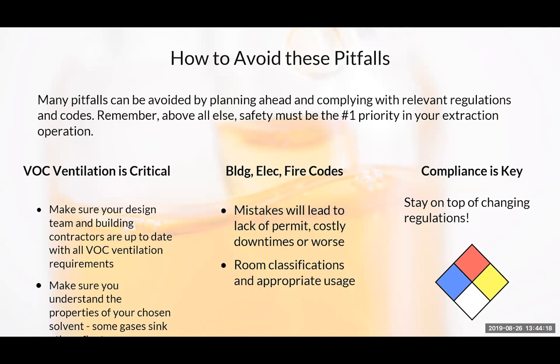It's pretty straightforward. The pitfalls we've already covered some of earlier. The design obviously is not having all ventilation requirements taken into account, especially when you have a process solvents facility. Some gases float, some sink, so depending on how the facility is designed and what solvents you're using, there are differing design methodologies for each one.